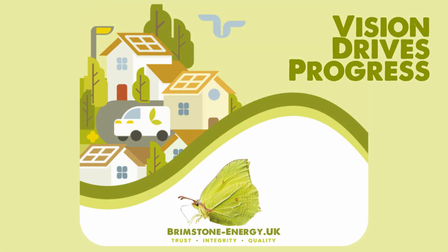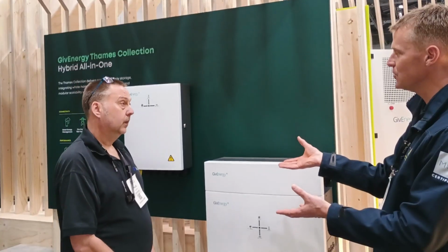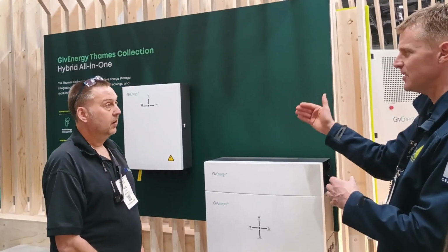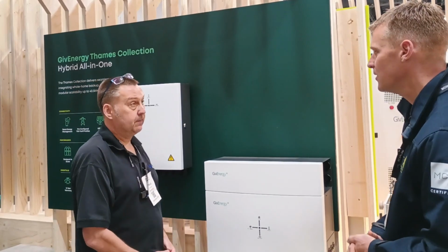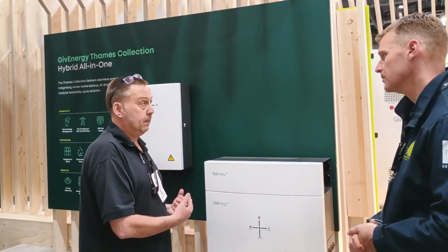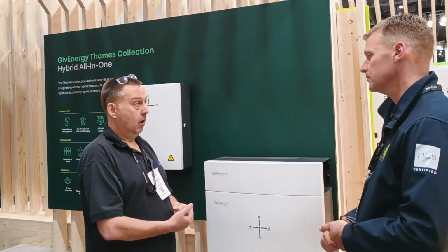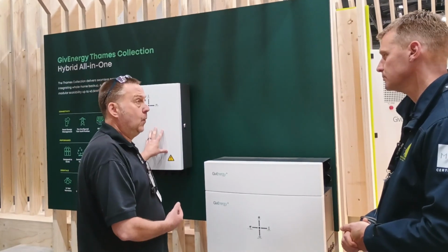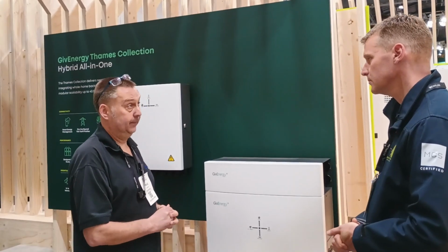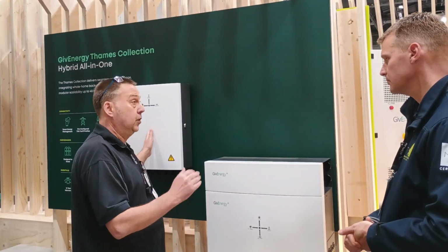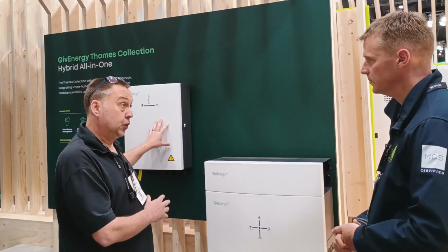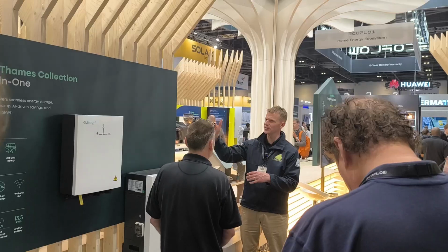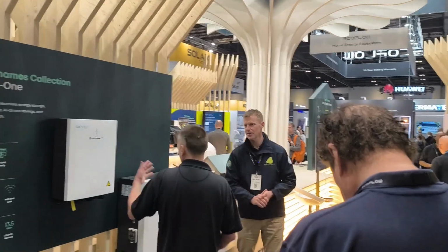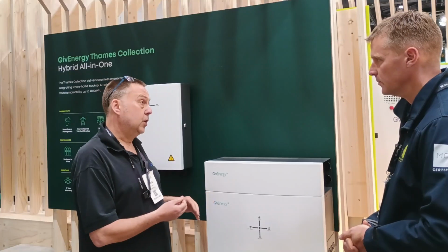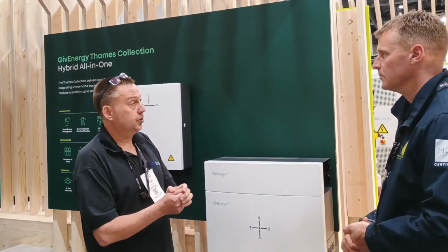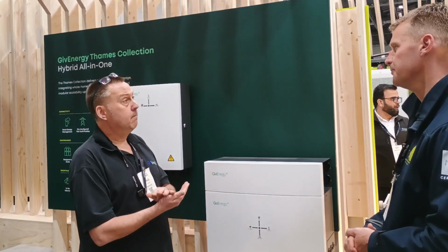Where else could this go in the future, do you think? I mean, this is already incorporating a huge number of features. What is the sort of 5-year vision for this, do you think? You could have extra smart loads. You could have modulated smart loads, where you can vary the power on a smart load. You could then have the gateway controlling the car charger power directly. So you'd have a connection between the gateway and your car charger. So your car charger would be plugged in as normal on a 240 volt supply. You then have a comms cable between the gateway and your car charger. And that surplus energy, you could then tell the charger what it is you want to do. Instead of just being on-off, you could then modulate that power.